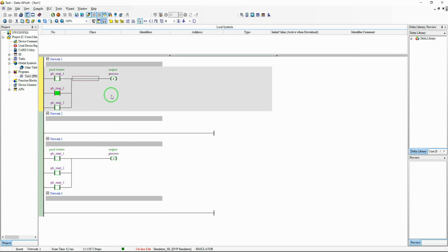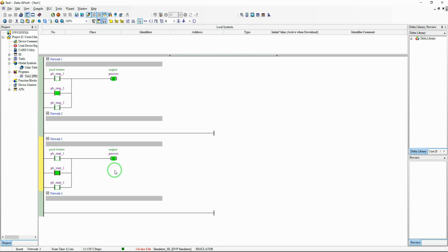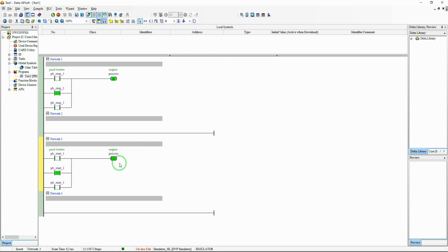The set function must be on the top, because now the PLC is enabling resetting at this point, and at this point it is setting, and the HMI is transferred the last state of this bit, which is at the end of the program. So this is the last network of the program, so the last state is on, even if it was off at this point.